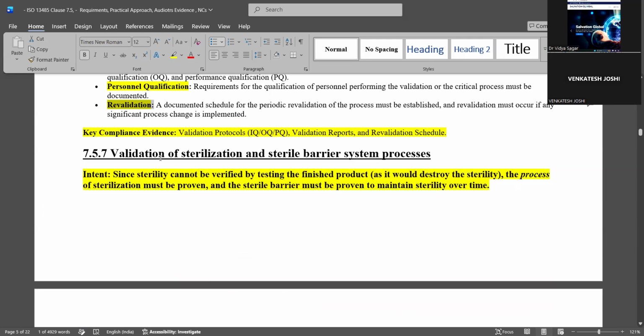So this sterilization validation has to be carried out, because you can't do verification of sterilization. After sterilization, you can't test every device. If you tested every device for sterility, there wouldn't be any devices left. It's not like you do 100% testing of whether the device is sterile or not. You have a sampling plan: out of 1,000, I'll take 1% or 2% and test it for sterility. But how do we know the other 99% are also sterile? To prove it, we do validation.